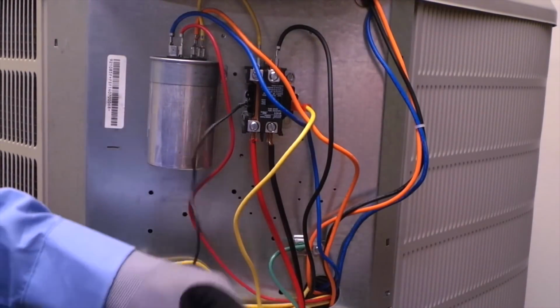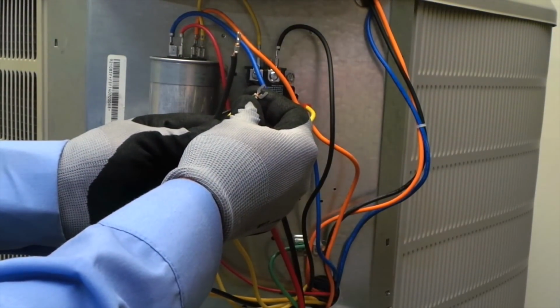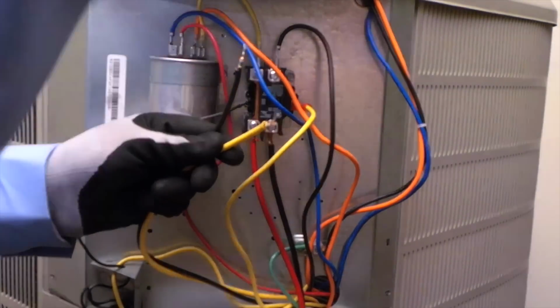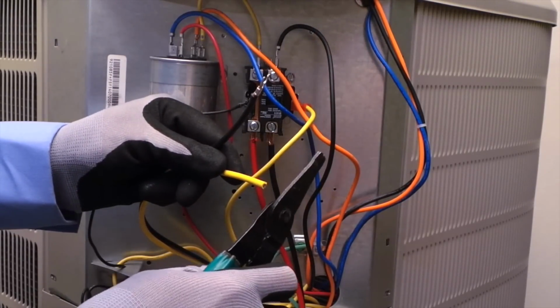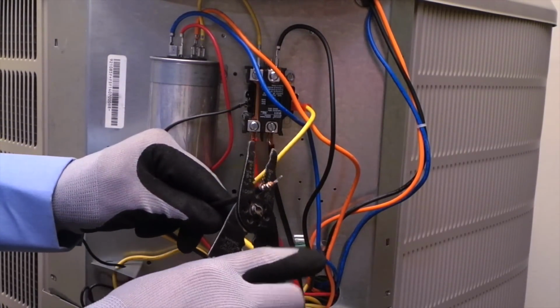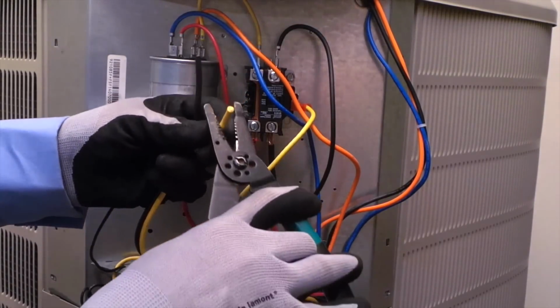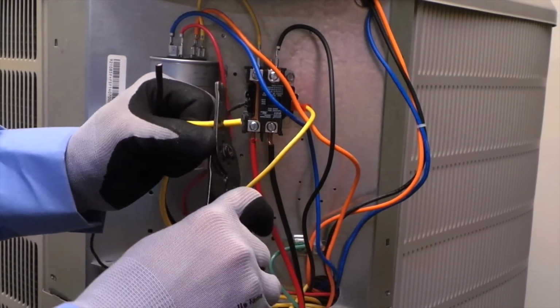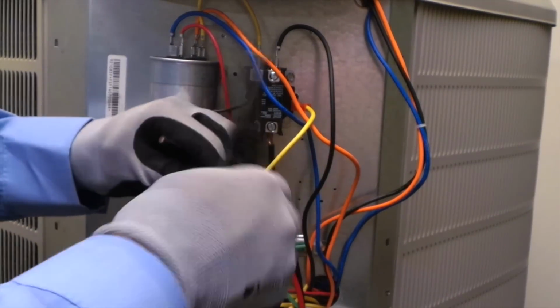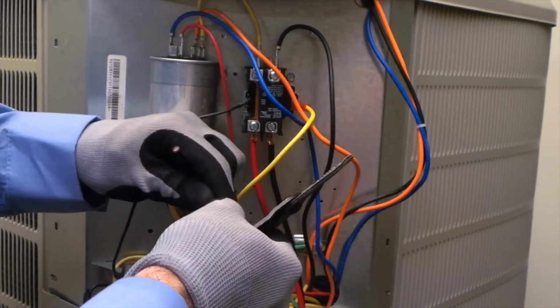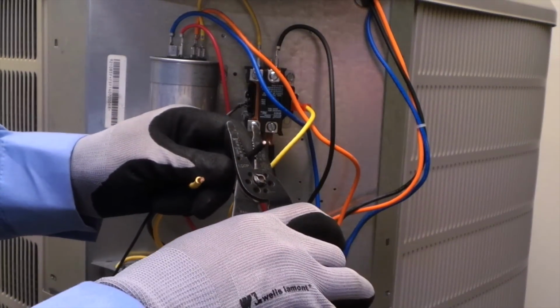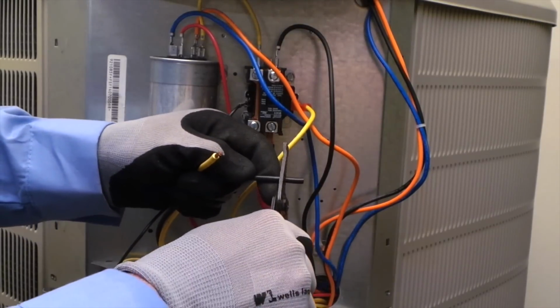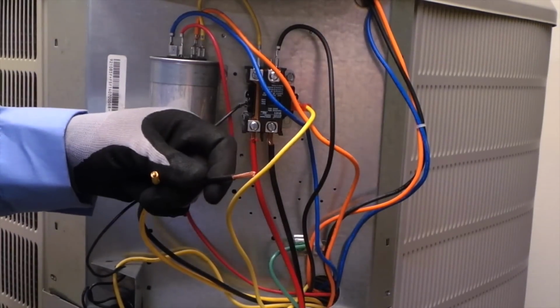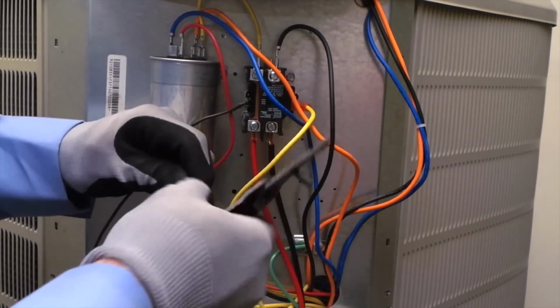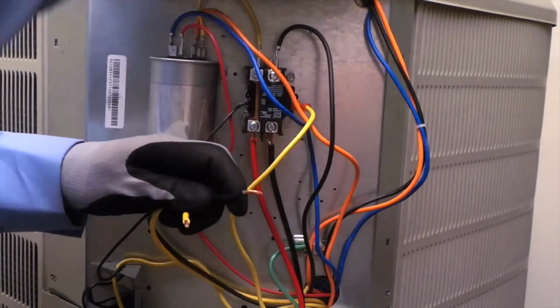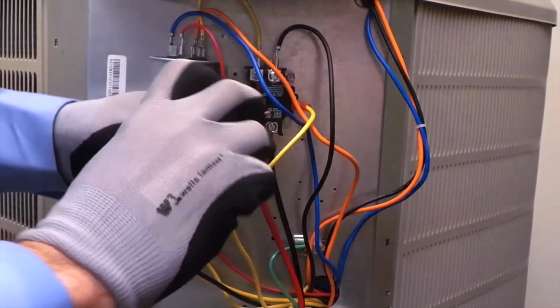Now we're going to make those adjustments in our wiring to accommodate for the lugs on the top of the terminals. Notice these wires coming from the compressor have crimped on terminals, so we're going to snip those off and strip these wires back about 1/2 inch so that they can be inserted into our lugs on the load side of our contactor. If you'll notice, our wires are black and yellow. The black wire comes from the common terminal on the compressor. The yellow wire comes from the run terminal of our compressor. These wires may not be the same color as the wires in your unit. If you have questions, consult your wiring diagram.